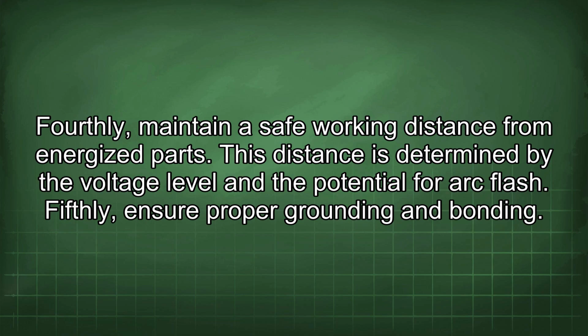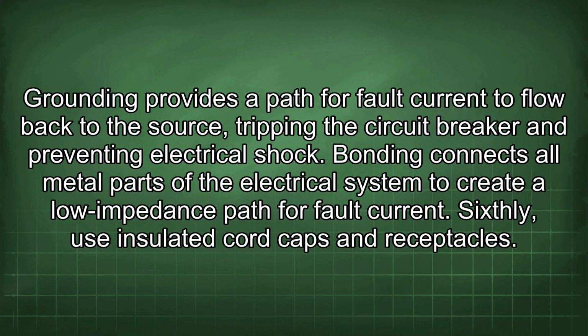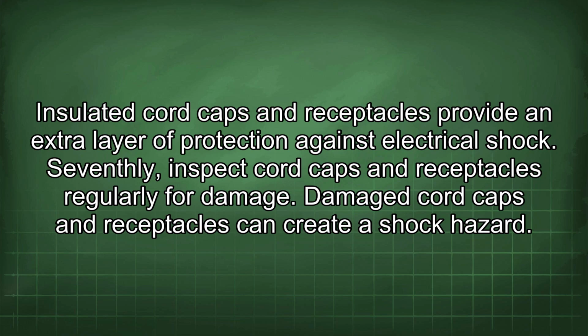Fifthly, ensure proper grounding and bonding. Grounding provides a path for fault current to flow back to the source, tripping the circuit breaker and preventing electrical shock. Bonding connects all metal parts of the electrical system to create a low impedance path for fault current. Sixthly, use insulated cord caps and receptacles. Insulated cord caps and receptacles provide an extra layer of protection against electrical shock. Seventhly, inspect cord caps and receptacles regularly for damage. Damaged cord caps and receptacles can create a shock hazard.